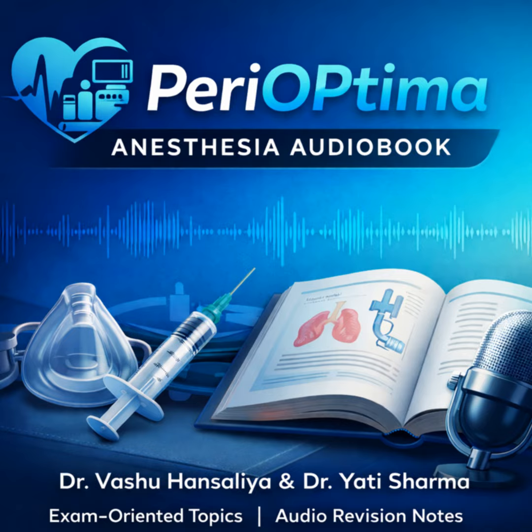And the other side of the coin, systems with an absorber. Exactly. These are the rebreathing systems, and really we're talking about the circle system. It uses a chemical absorbent, soda lime or baralyme, to remove CO2 chemically. This allows a patient to rebreathe the expensive volatile agent, which also helps conserve heat and humidity. That distinction, that fork in the road, directly leads to the second crucial layer of classification, rebreathing versus non-rebreathing. This is paramount because it dictates the second vital clinical factor you have to manage, the fresh gas flow requirements.